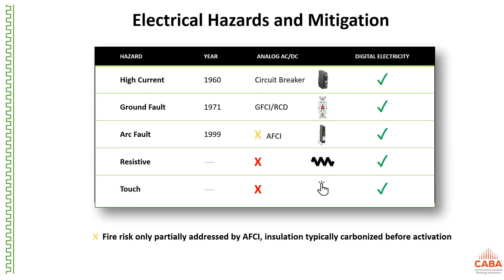It's just a heater that appears in the middle of your wall and starts fires. Digital electricity has the ability to sense that type of fault, as well as human touch faults. Today, a ground fault interrupter can protect a human if you bypass the common in a 3-wire connection and come through a ground surface. But if you touch the black and the white, the two hot wires in a 3-wire circuit, it doesn't know the difference between you and a vacuum cleaner or something else drawing the load. Digital electricity is very unique in that it can separate a human touch element from the regular load that's on those wires.